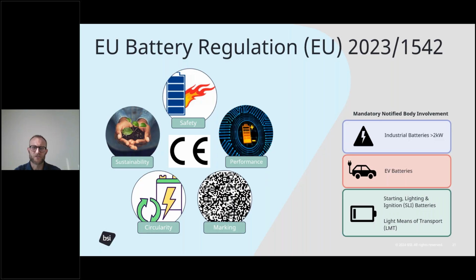The actual construction of larger batteries is multiple cells in a pack, and it may be very difficult to detect a single cell going into thermal runaway in that larger pack. When they do catch fire, the release of energy can be sudden and violent. Suppression, where the extinguishing can actually be applied to the battery, then stops propagation of that fire.